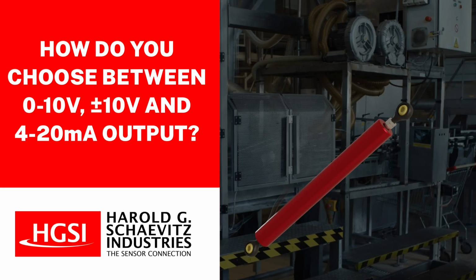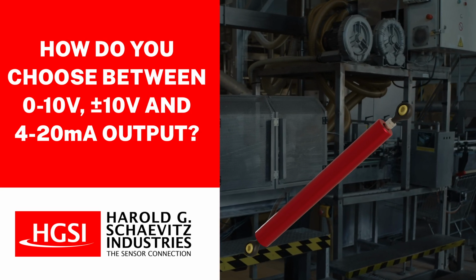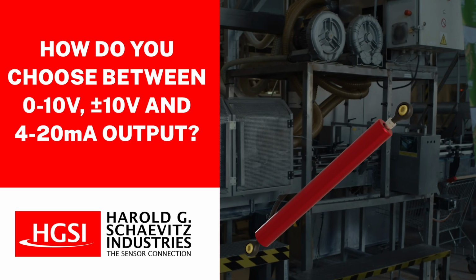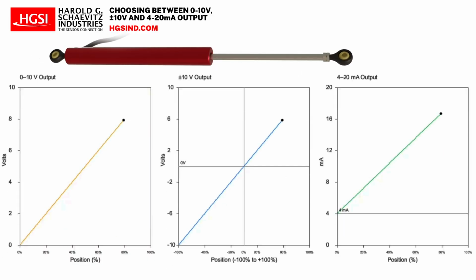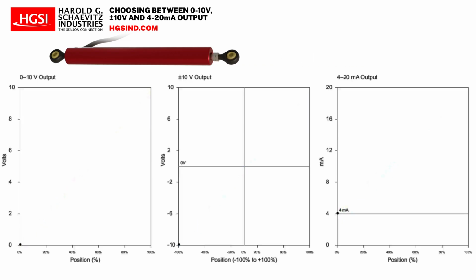A common question we hear when selecting industrial sensors is how do you choose between a 0 to 10 volt, plus or minus 10 volt, and 4 to 20 milliamp output? These are some of the most common analog signal formats used by industrial sensors, such as position, pressure, and temperature sensors, to transmit measurement data to control systems.